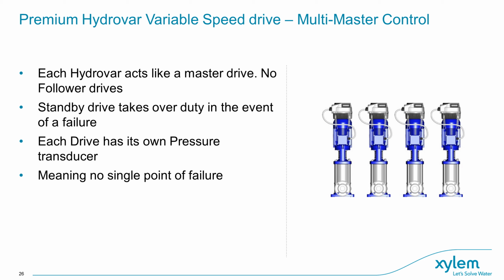Again, to ensure that there is no single point of failure, each drive has its own pressure transducer, so if there is ever an issue with the sensor, the set would not stop working. Just to reiterate that point, not all booster sets on the market work in this way, with many relying on one master drive or panel to control other follower drives.